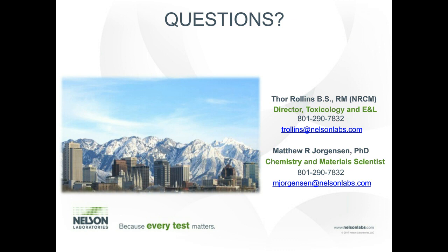I know Matt wants to answer this one, but I'm taking it from him because it really depends. I know no one likes the word depends, but you need to be able to prove that the materials are the same. Like I talked about, not all HDPEs or not all silicones are the same, even if they are supposed to be the same, even if they say they're identical. You really need to be able to prove that the components are leaching the same compounds. So chemistry can help with that.